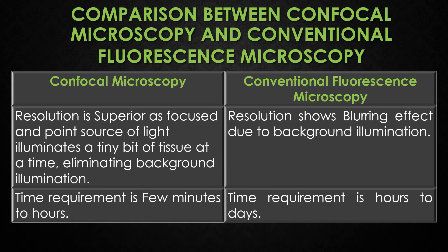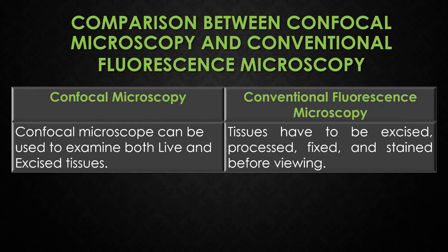The resolution is superior in confocal microscopy, as a focused point source of light illuminates a tiny area of tissue at a time, eliminating background illumination. Conventional fluorescence microscopy shows a blurring effect due to background illumination. The time requirement for confocal microscopy is a few minutes to hours, while conventional fluorescence microscopy requires half a day to days. Finally, confocal microscopes can examine both live and excised tissues, whereas in conventional fluorescence microscopy tissues must be excised, processed, fixed, and stained before viewing.